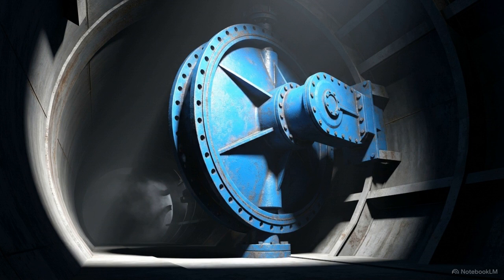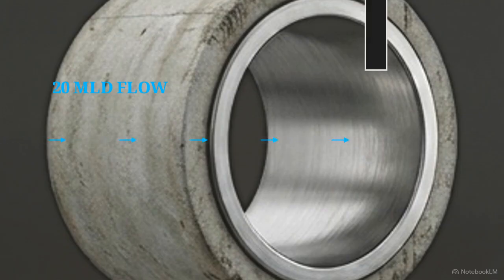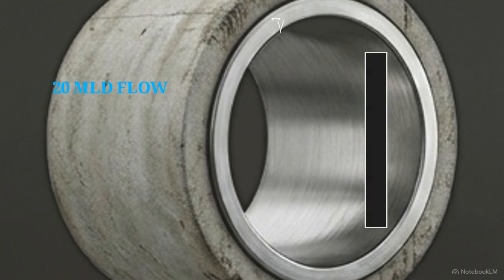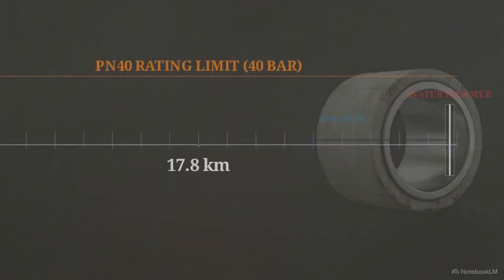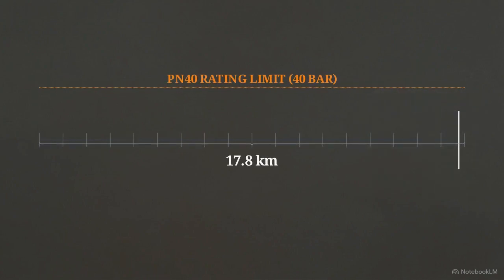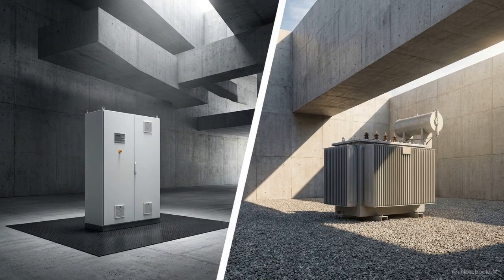Injecting such high levels of energy too rapidly, or losing that energy suddenly, will trigger catastrophic hydraulic shock. When thousands of tons of moving water hit a stationary barrier, the kinetic energy compresses and generates a destructive pressure spike known as water hammer. This waveform reflects, compounding in amplitude as it travels backward down 17.8 kilometers of PN40 steel pipe. Protecting a pipeline from bursting under these forces dictates every design choice in the facility.